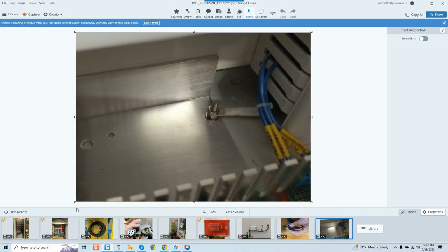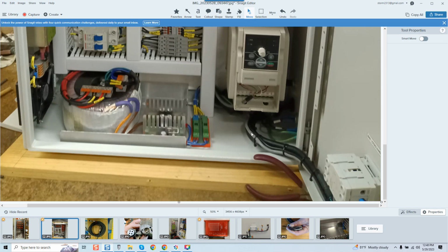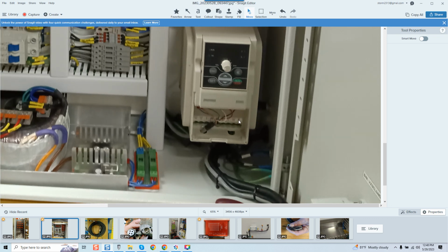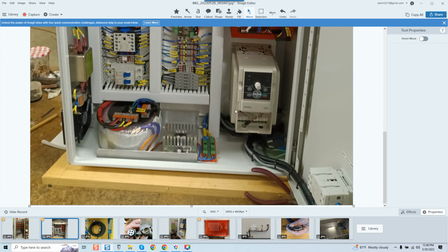And that puts me to another point to prove that that spindle cable is not double shielded, because as we come in here, you don't see a ground bus to where this is terminalized at the VFD. None of these leads come over to earth ground where you would see a drain. And you can see there's the E right there. Zoom in a little more. It's kind of blurry, but you get the picture. You can see there's no shield drain coming into that, and there's also no shield drain coming into the base chassis if they wanted to ground it to the chassis. So what that tells you is this system is only having one ground.